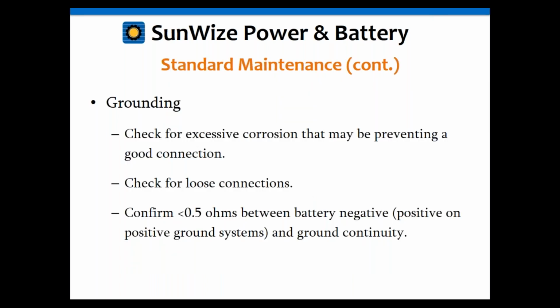Grounding, another one that's very important. Actually, we're about to release a new tech note on grounding, just because they can be a problem as well. And again, what you're looking for there is corrosion, something that will be preventing a good ground. You also want to check for loose connections again. Same thing, you've got thermal cycling going on. These are all things that can be checked and corrected on a regular maintenance schedule.